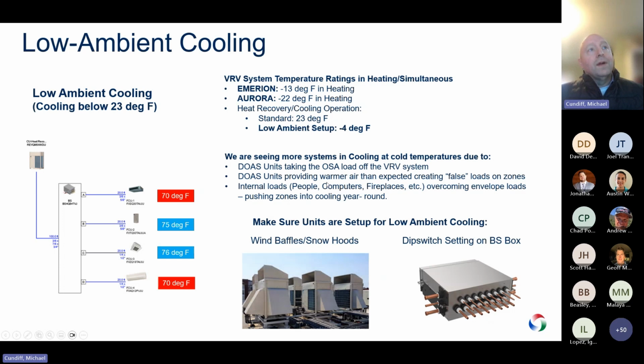Sometimes you have DOAS units providing warmer air than expected, creating false loads on zones. So I've seen some buildings that we go out to where the DOAS systems are providing air warmer than set point. That's creating issues around the units going into cooling and wasting energy for some of these projects. And then you have internal loads, people, computers, fireplaces, overcoming envelope loads, maybe due to much more stringent construction standards with insulation and that kind of thing.